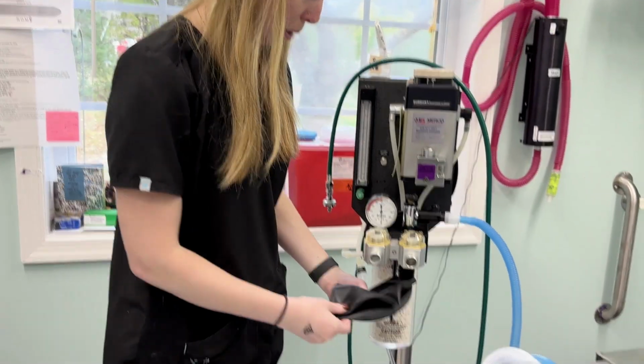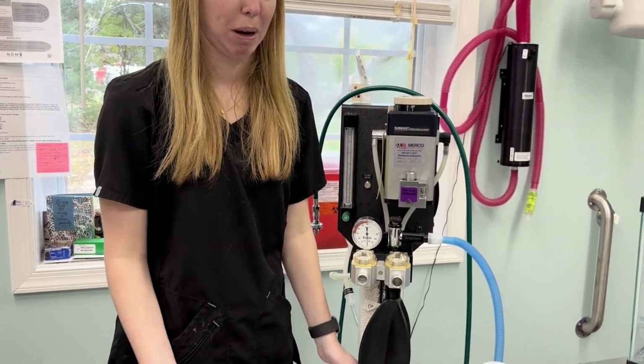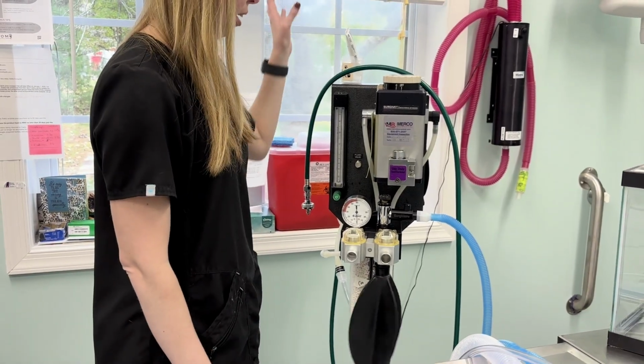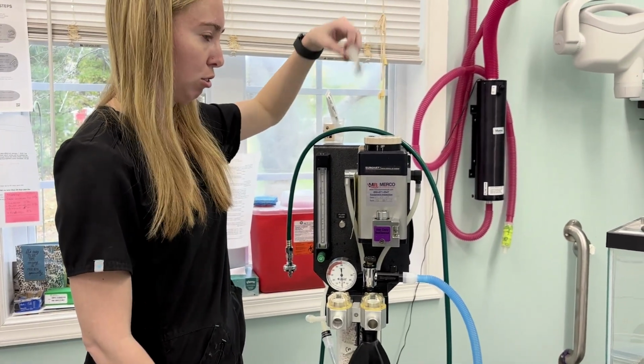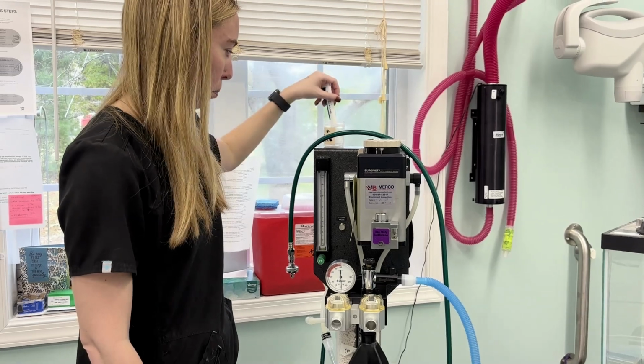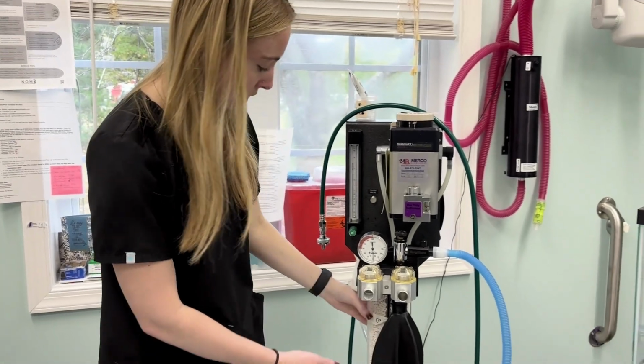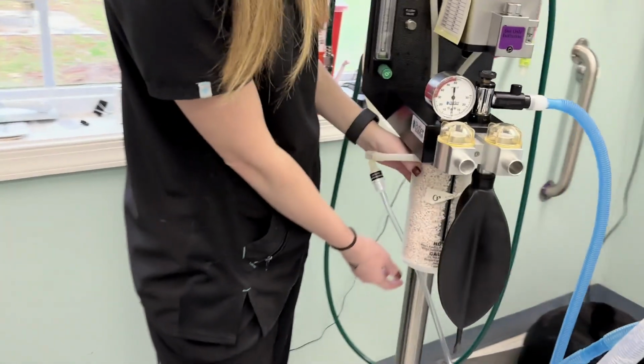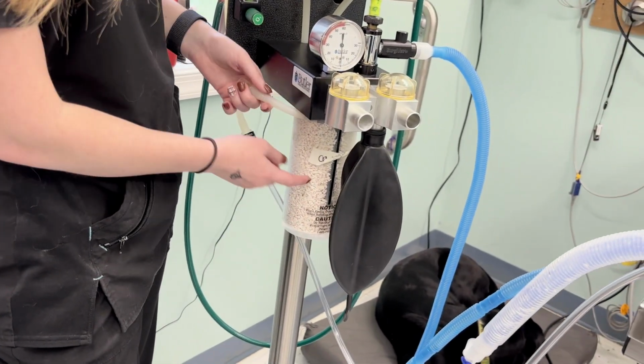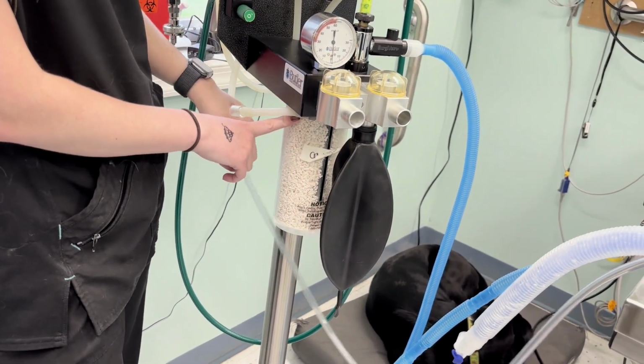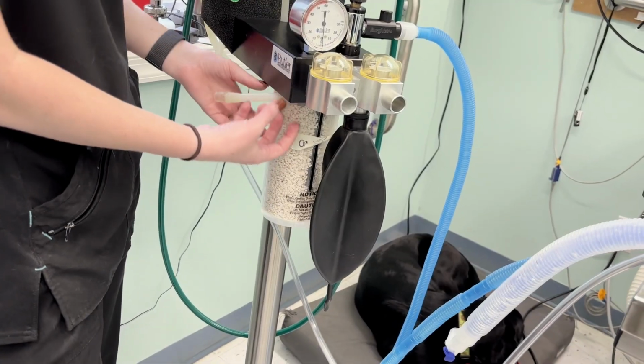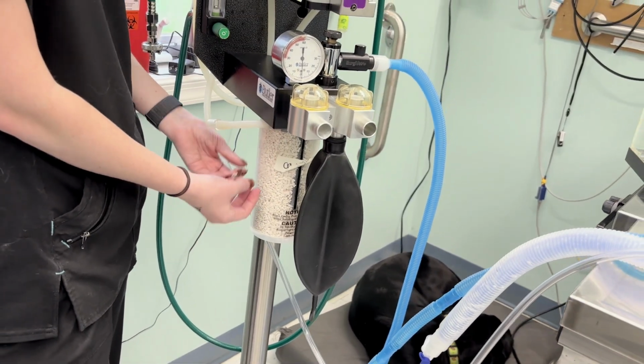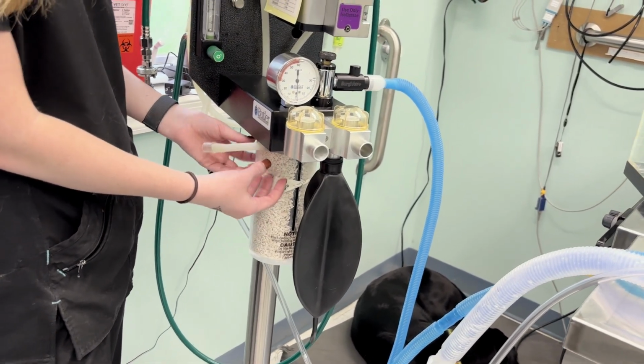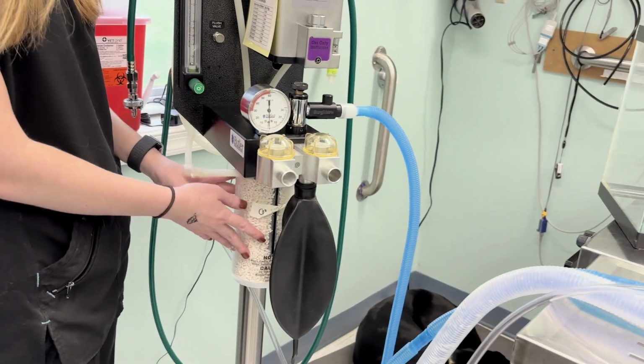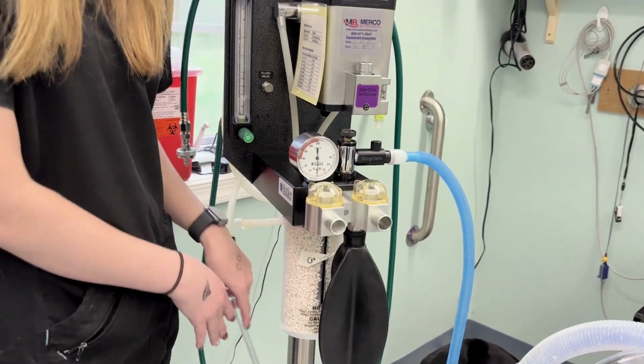We do have other size bags, so according to the patient weight, you can change the bag. And then we also have our tube inflator and our lube up here that we can keep. And then this is our CO2 absorbent canister. So these pellets will change to purple when the granules have pulled enough CO2 that they've used up their use as far as that goes, and they're very brittle, so it does need to be changed. We change them about weekly. And that's it. Thank you.